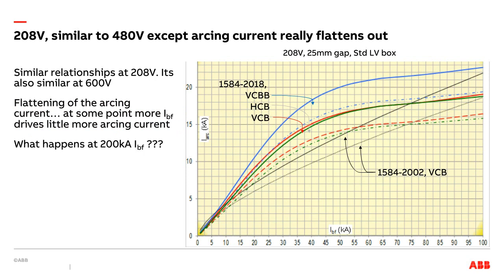Here's another calculation, in this case at 208 volts, 25 millimeter gap, standard low voltage box. Again, your arcing currents typically are higher, but notice how they flatten out, which means that if you are calculating an arc flash for very high fault current systems, now you have a different scenario where your protection may act very differently than you expected it to, and you may get some widely different results. But in this middle range, it kind of holds true for almost all voltages, all gaps. The new study will give you a higher arcing current than the old study.